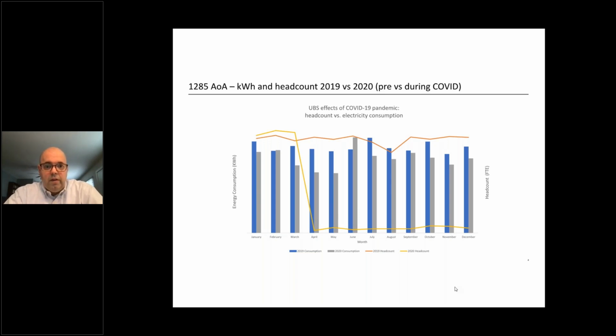One other factor to consider is that we may not have enough granular data at the sub-meter level to fully explain the pattern. We have about 850,000 square feet across 1285, across 19 floors, and while we do have sub-meters on some floors, some cover multiple floors, making it harder to take a deeper dive into what's going on. At minimum, more sub-meters, with at least one per floor, would help tease out the causes of outlier dips or spikes. While there would be value in more granular monitoring, the rate of return isn't necessarily great compared to the cost of implementing such a solution.